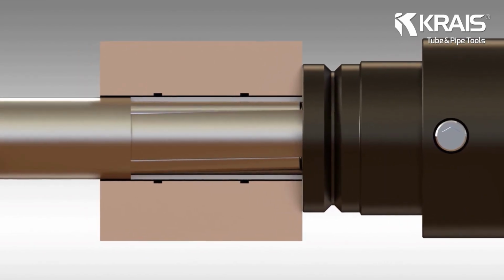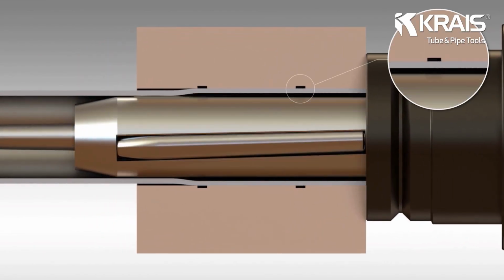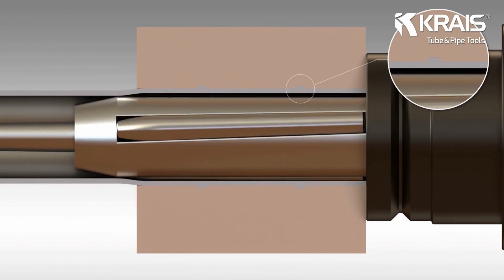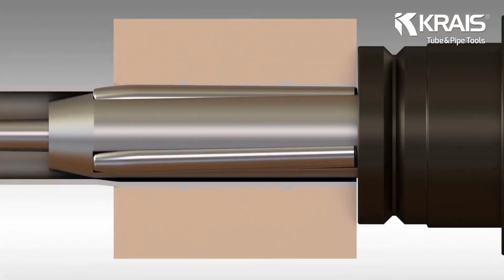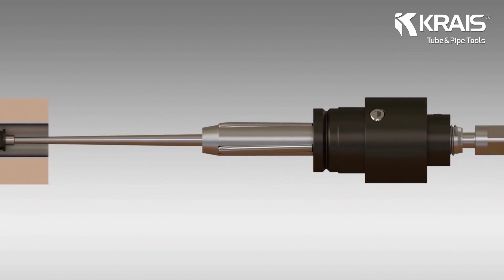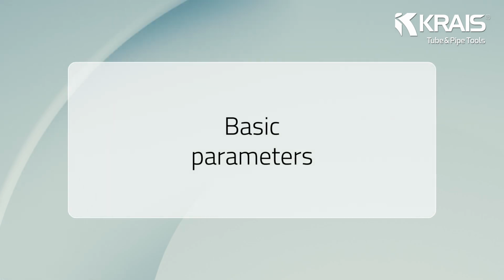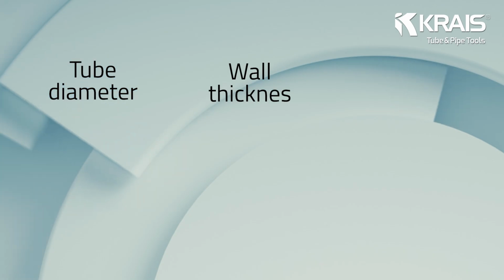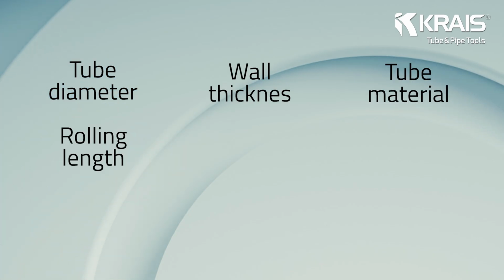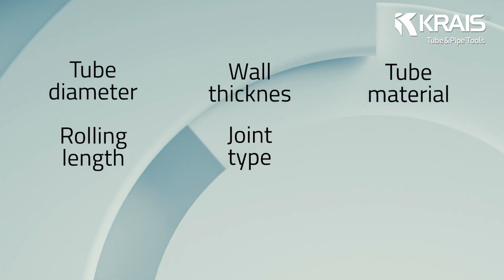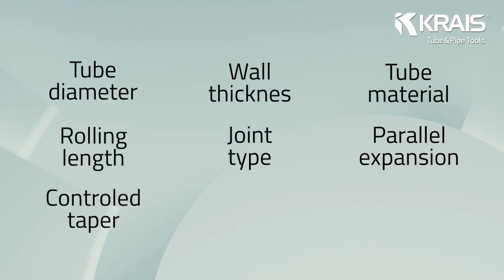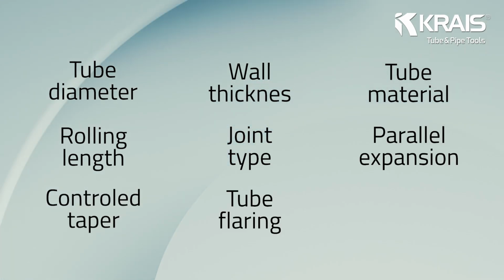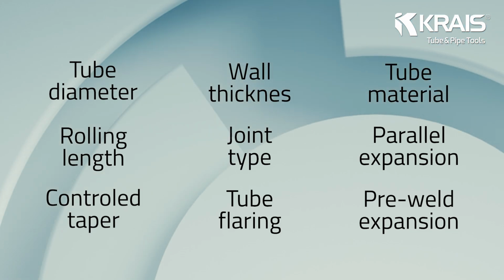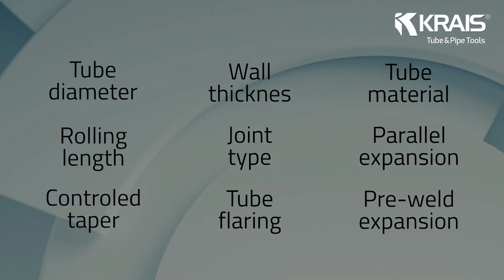KRAIS expanders are manufactured from high-grade tool steel, utilizing modern heat treatment and a precise grinding process to ensure maximum durability and performance. Tool selection is driven primarily by tube outside diameter, OD, wall thickness, tube material, required roll length, and the joint type: parallel expansion, controlled taper, expansion with flaring, pre-weld expansion, or additional mechanical locking features.